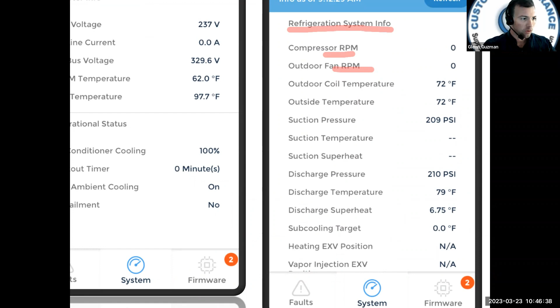Now you have to periodically refresh the app, because every time you see this data, it's just kind of a snapshot of what's happening at that current moment. So about every 30 seconds or so, you can hit refresh and that'll pull new data. We want to see that—when it starts up, my suction pressure is high, and I want to see it start coming down. That helps me know the unit is working as it should. I like to see my superheat begin to build, that sort of thing. So it's just a lot of information there.